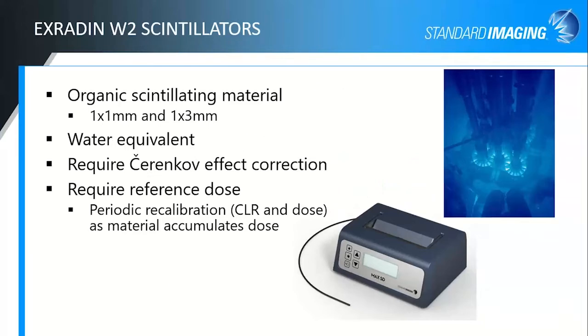So the newer technology that I'd love to talk to you about, if you haven't heard of them, are the Exradin scintillators. So the W2 scintillator is the one that's designed for scanning. It's an organic scintillating material. We have fibers with a 1 by 1 millimeter tip and a 1 by 3 millimeter tip. And the reason for that actually is the 1x1 gets you that resolution, especially that orientation independent sort of resolution. The 1x3 matches our original scintillator, which was the W1. And also gives you a little bit higher signal level for those fields where that volume averaging is acceptable, so that you have a little bit less concern about your signal to noise ratio.